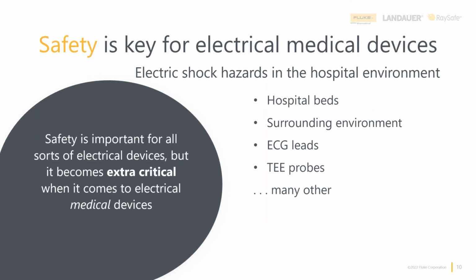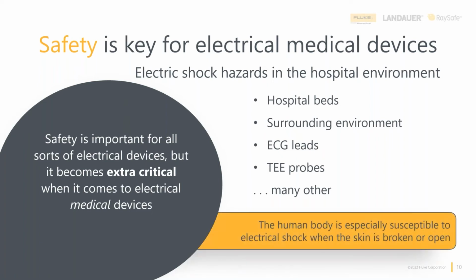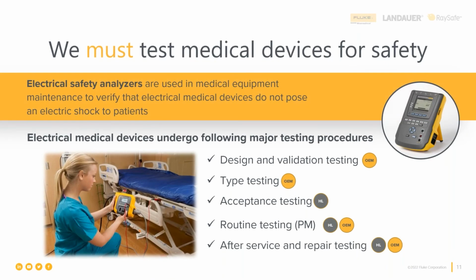So, as I said, due to this big study, we discovered that anything that we plug into the wall, actually anything that operates on electrical power, can produce sufficient leakage current that if it's introduced directly into the heart, will cause injury or death to the patient. So it's really important that we test hospital beds, the surrounding environment, ECG leads, or other kinds of continuously conductive patient connections, transesophageal echocardiographic probes, and we'll talk about that a little bit more later, and many others. So even if it's battery powered, it still can produce enough leakage current that it can harm the patient. So we need to really do these tests.